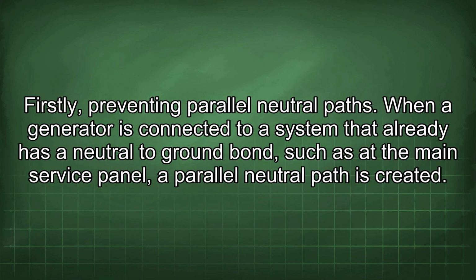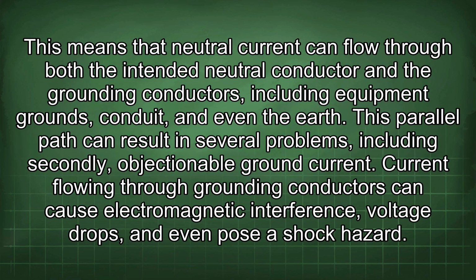Firstly, preventing parallel neutral paths. When a generator is connected to a system that already has a neutral to ground bond, such as at the main service panel, a parallel neutral path is created. This means that neutral current can flow through both the intended neutral conductor and the grounding conductors, including equipment grounds, conduit, and even the earth. This parallel path can result in several problems, including, secondly, objectionable ground current.